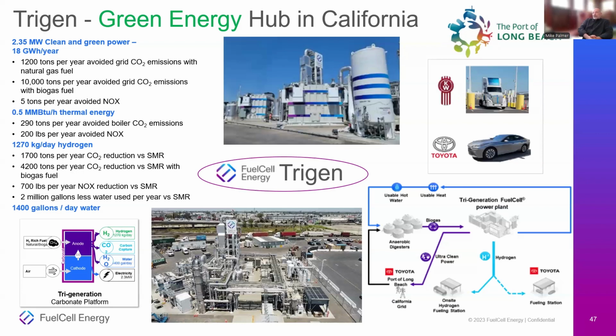One thing that happens at these ports is when big ships dock, they go into what's called hoteling mode — usually running diesels for power while sitting at the dock. But in California, like many states now, you're not allowed to use diesels for hoteling because of emissions, so you have to use shore power. Shore power in California is very expensive, so Toyota wanted a way to provide green power to support their ships coming in, so they didn't have to go to the grid.